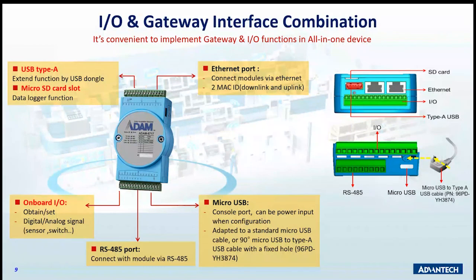The only caveat for using the USB with this device is that if you're going to run anything on the USB port at the top, any additional devices or anything like that, you really need to be powering it from its power connector, the green Phoenix connector that comes with it, just because the USB spec does not allow for a very large current to be pulled through it. So if you're going to attach powered devices, it's more advisable to have the module's inbuilt power supply to supply that power.